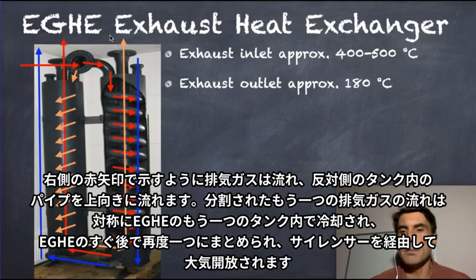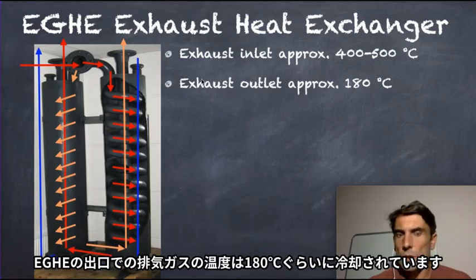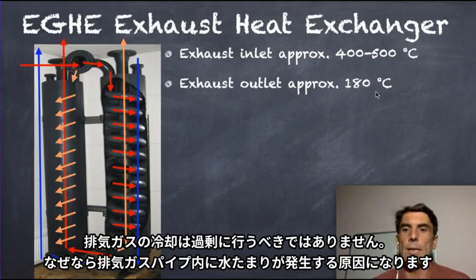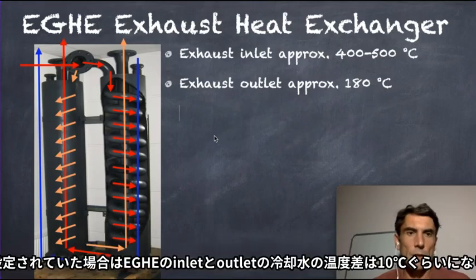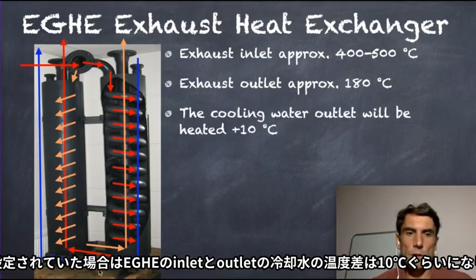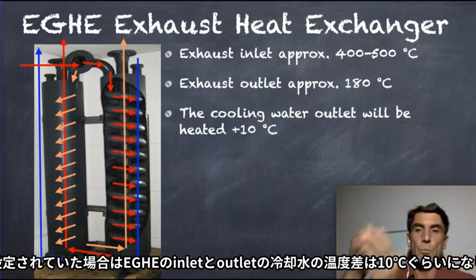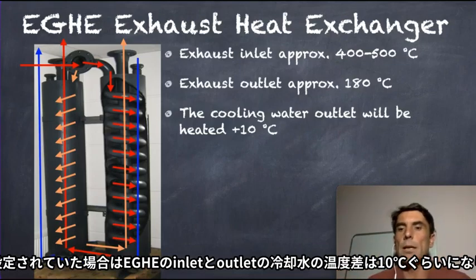Both pipes later on will be connected to a center pipe and go to the silencer and up into the air. So the exhaust gas outlet will be approximately 180 degrees. We shouldn't cool down the exhaust gas too much, otherwise we get into the area where we get condensate in the exhaust gas pipe. With the system here, we're running the water next to the pipes of the exhaust gas, heating up the water. The water runs through into the next tank, and runs out of that tank. That means we're heating up from the exhaust gas from the first turn pipe to the next turn pipe, and can remove an additional heat of plus 10 degrees forward flow temperature. So we're getting an additional heat from the exhaust gas, which we supply to the primary circle of the CHP, which then gets supplied to the client if needed.